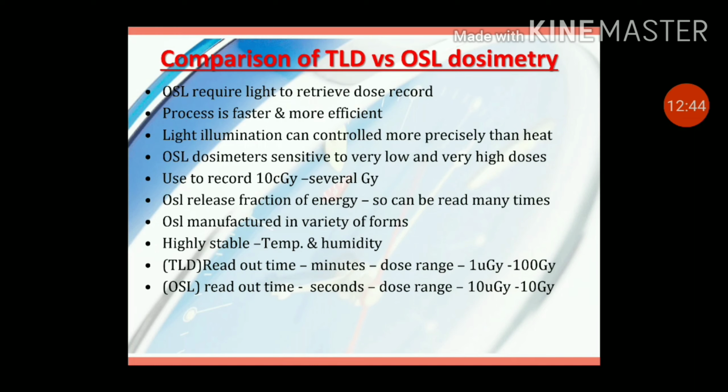So readout time of TLD is in minutes. Dose range is 1 microgray to 100 gray. OSLD readout time is very short, that is in seconds, a few seconds, like 1 to 2 seconds. The dose range is 10 microgray to 10 gray.